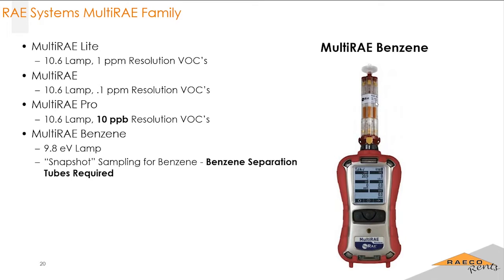And then we have the benzene equipment. Benzene is a very, very dangerous compound. For that reason, when you're hoping to detect benzene, you need to use what they call benzene separation tubes. This tube filters out everything that is not benzene and takes a snapshot reading of the concentration. They are single-use tubes, just something to note—each tube is needed to get your benzene concentration.